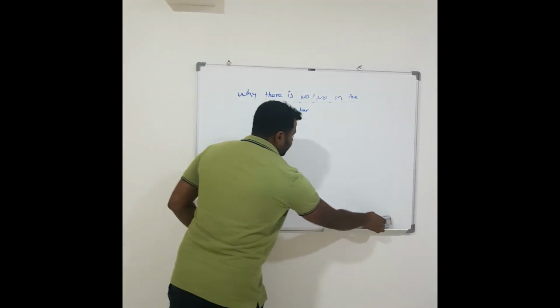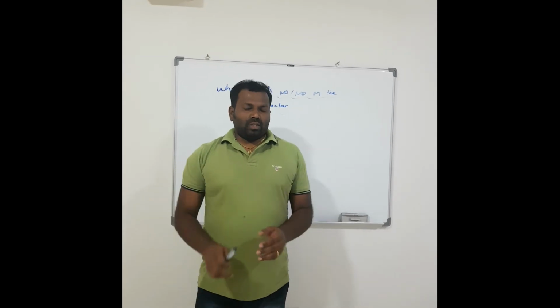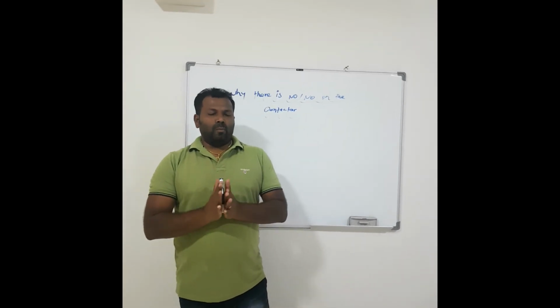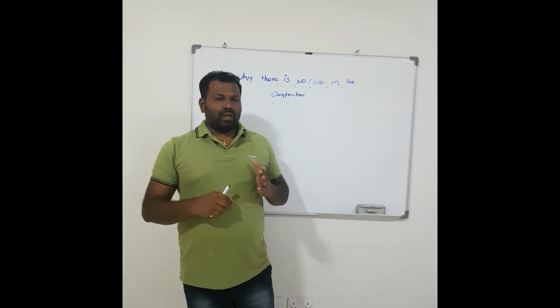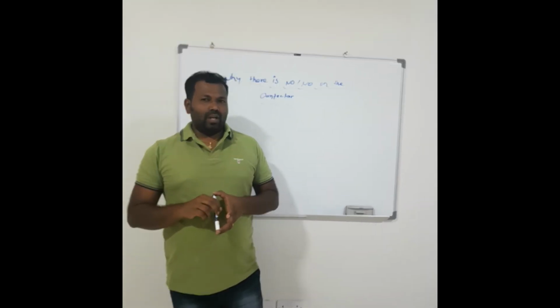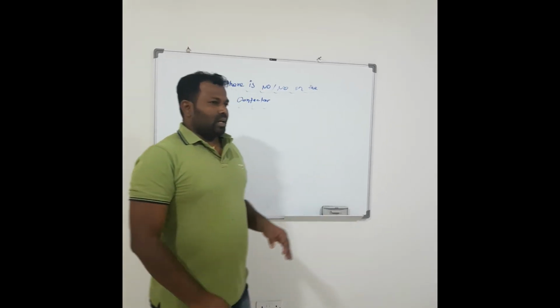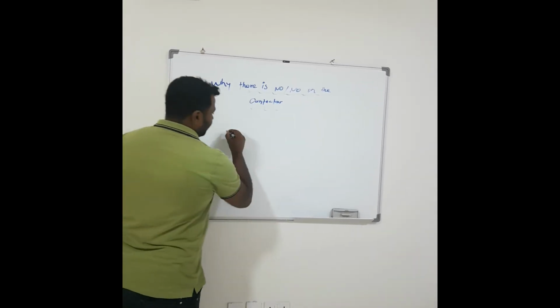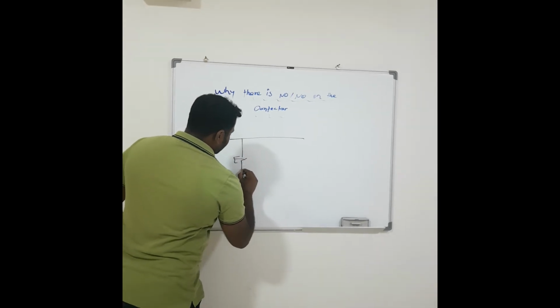This NO contact is commonly used in push button applications. Most starters are operated through push buttons. Once this push button is pressed, the NO contact will hold the coil supply continuously till the stop button is pressed. We will see how this will work. The same starter is connected with two push buttons, start and stop.